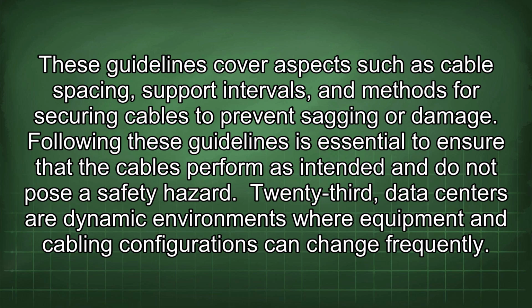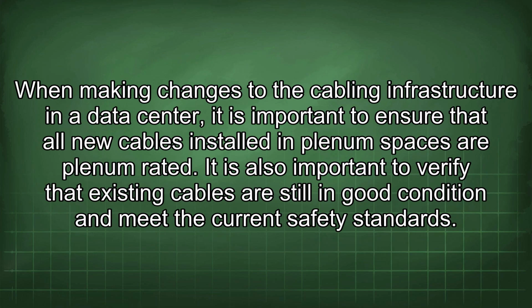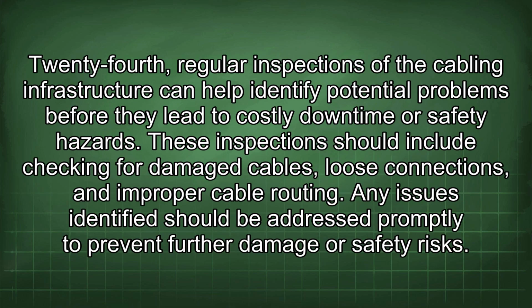23rd, data centers are dynamic environments where equipment and cabling configurations can change frequently. When making changes to the cabling infrastructure in a data center, it is important to ensure that all new cables installed in Plenum spaces are Plenum rated. It is also important to verify that the existing cables are still in good condition and meet the current safety standards.